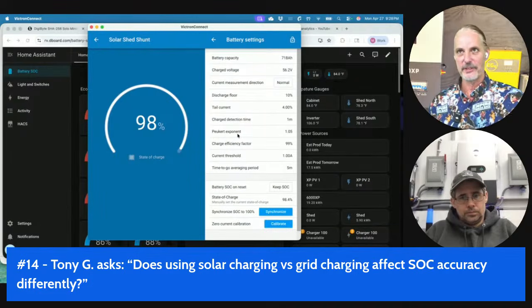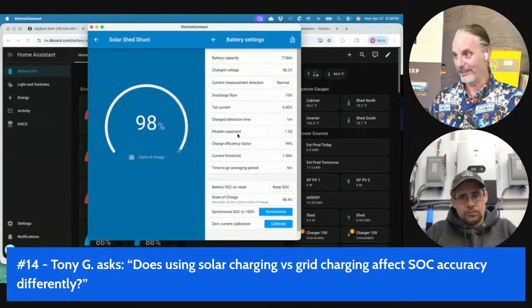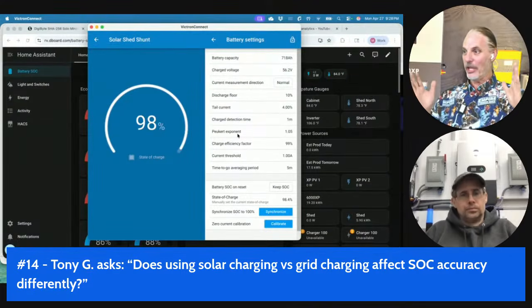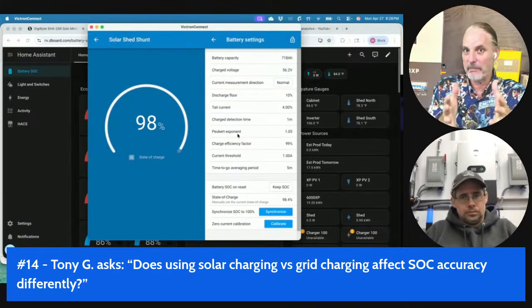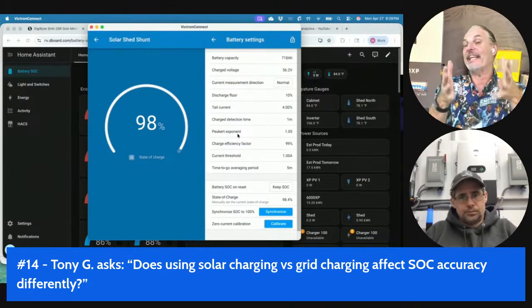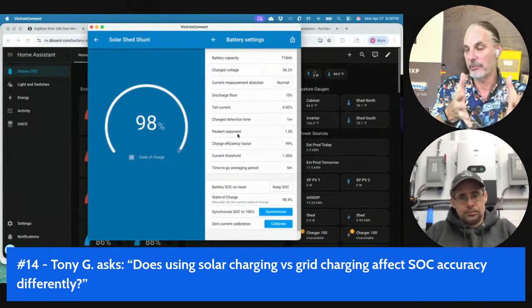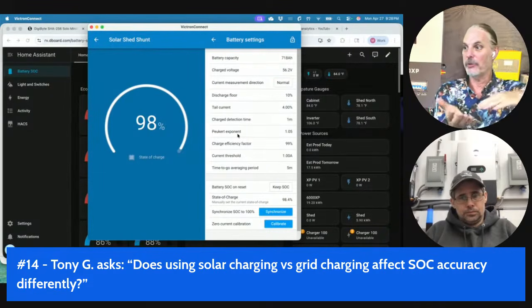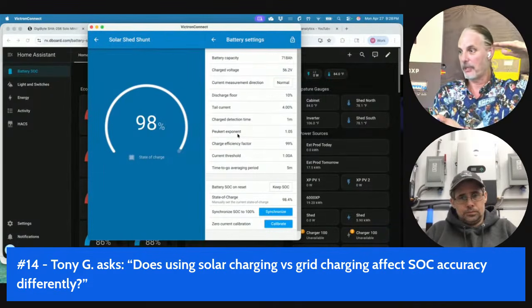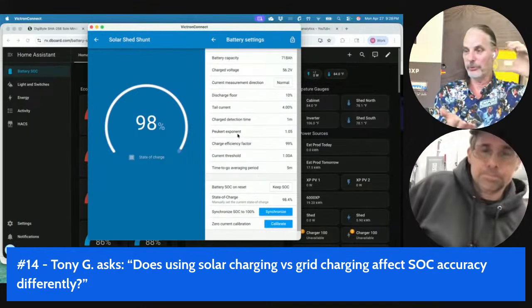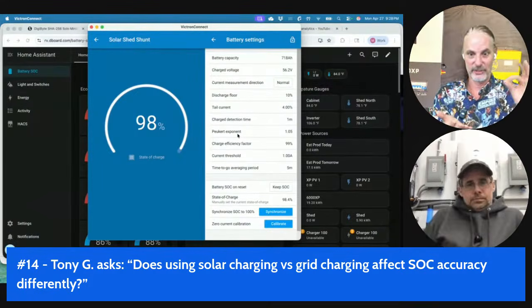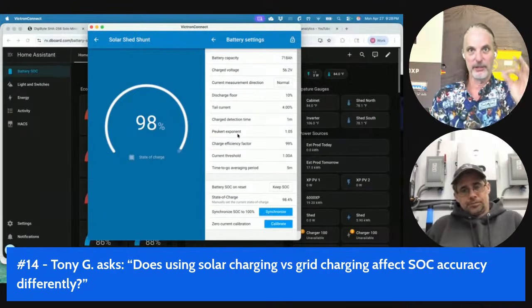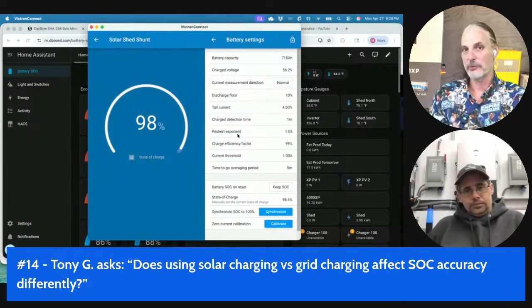This is basically 0.1%. And when you use lead acid, this can be as much as 20%. What happens is you have this big influx of power with a lead acid battery, but it can't absorb it as fast as you're providing it. So there are diminishing results depending on how fast you're putting the power in. The old chargers used to allow you to set this formula based on how it was going to absorb it.